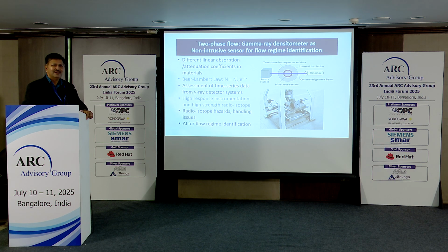Of course, the type of detection that we wanted for density measurement was a gamma ray based system with cesium isotope. The only thing we had to handle was an isotope strength of something like 1.6 to 2.1 curie, which is unheard of in the process industry, right? And for a high response system, we had used an yttrium aluminum perovskite scintillator based detector with this, so that we were able to really achieve that kind of detection response time.